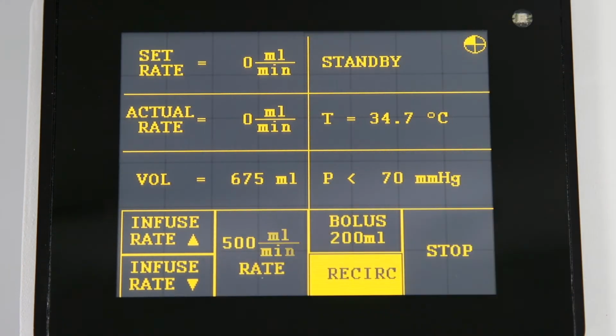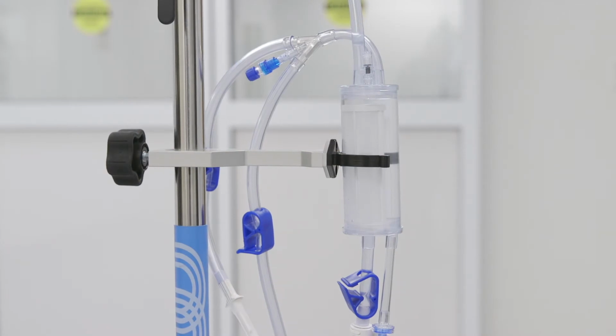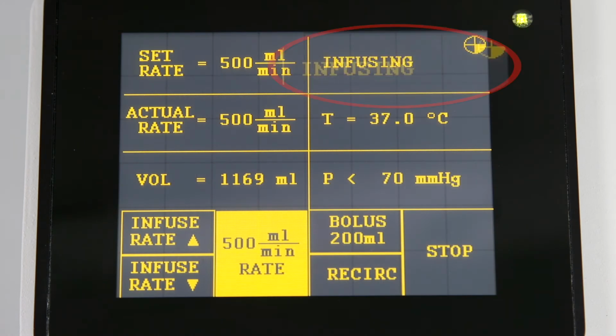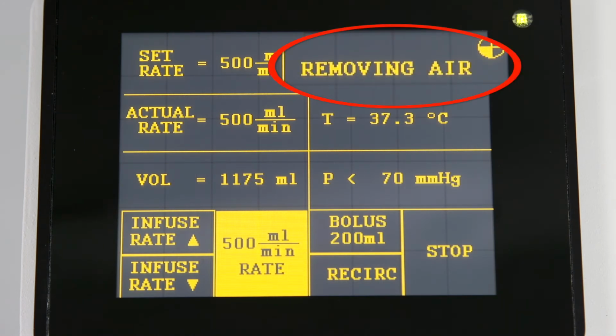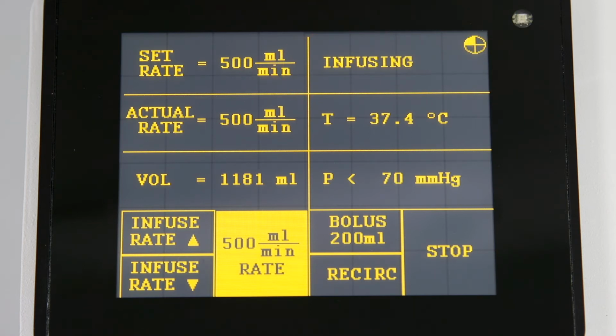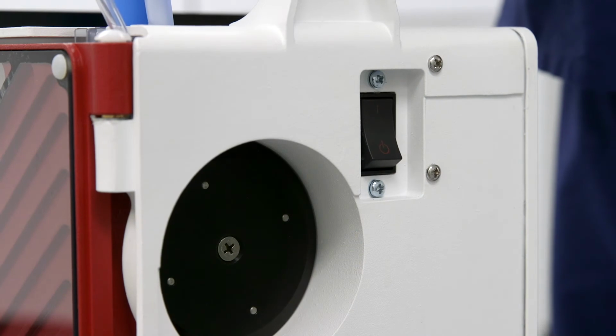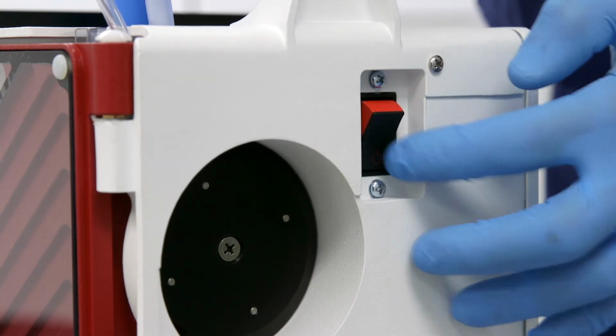Pressing the recirculation key will recirculate fluid through the reservoir and disposable circuit. This feature is used to warm and mix fluids and will automatically stop after 5 minutes. As fluids are warmed, gases are formed. The Belmont Rapid Infuser RI-2 will trap these gases within the system and automatically purge them into the atmosphere. When this occurs, "removing air" will be briefly displayed on the screen, and you may see bubbles escape through the recirculation or vent line. At the end of the procedure, be sure to disconnect from the patient and power down by turning off the power switch.